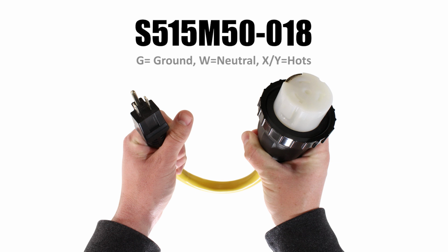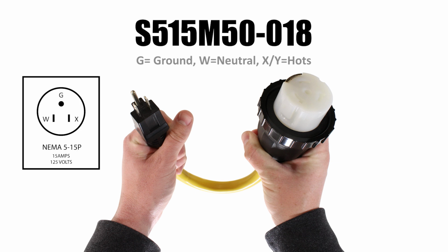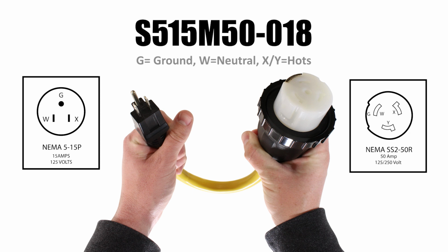So what exactly is this adapter? Our S515M50-018 goes from a NEMA 5-15 plug, which is a standard 15 amp plug with one hot, one neutral, and one ground, to a NEMA SS2-50 connector, which is called M50 in our part number to designate marine and RV 50 amp. The SS2-50 receptacle is a 50 amp connection that has two hots, a ground, and a neutral.